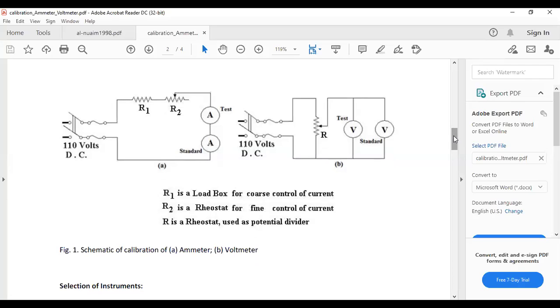So for this voltmeter calibration, as we are calibrating the voltmeter, we have to provide different voltages and see what the reading is in the test voltmeter and what the reading is in the standard voltmeter. Then we can calculate the error for the test voltmeter, isn't it? And for ammeter calibration, we have to provide different currents because an ammeter reads current. So how can we vary the current? By varying a series resistance, we can vary the current.